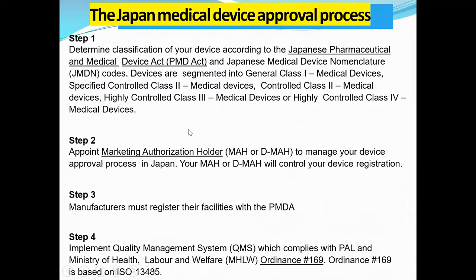So we have seen in the previous slide, you have to classify your own device as per this Japanese PMDA Act and GMDN codes, under which category you are falling, whether it is class 1, 2, 3 or 4. Then appoint a marketing authorization holder, that is MAH, to manage your device approval process in Japan. Of course, the Japanese language is very difficult, like China. Whenever you go into China, it's very difficult. There is always a language barrier. So you have to appoint a Japanese agent, what we call the marketing authorization holder in Japan, to manage your device approval process.